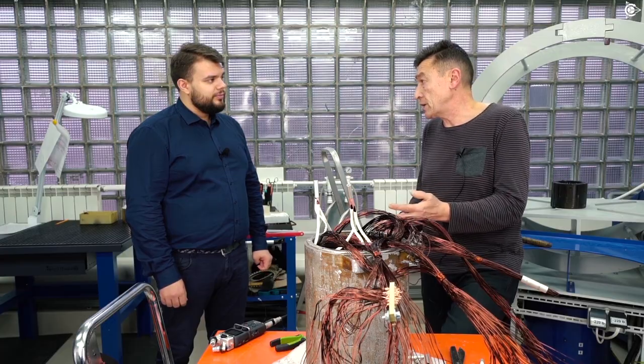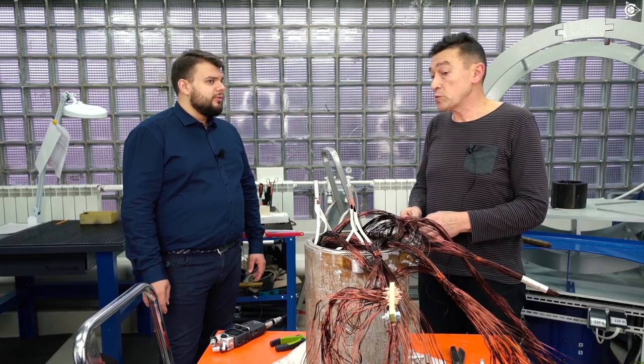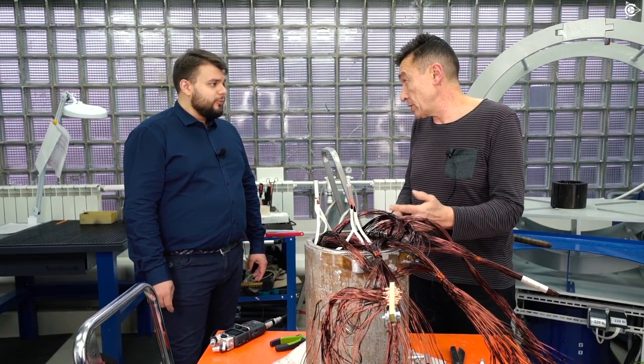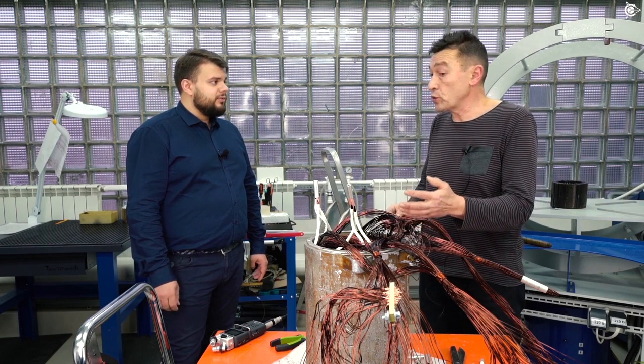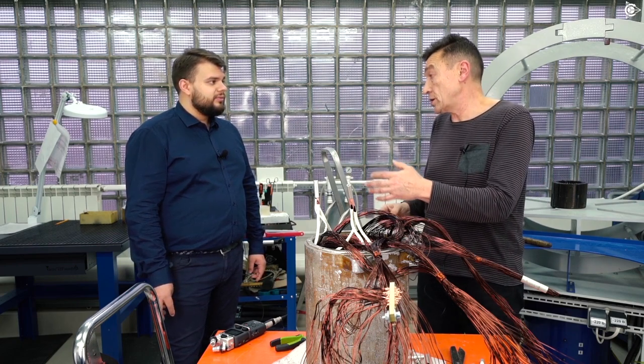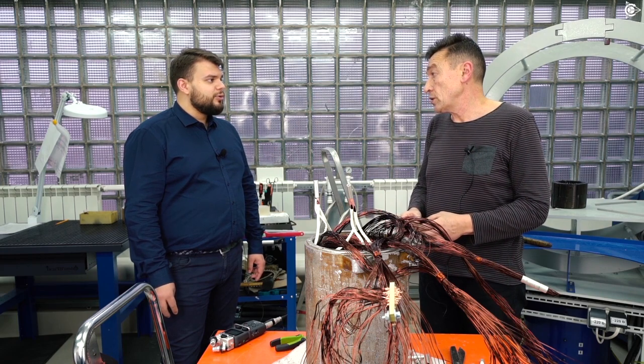Putting it on the compressor is the right approach. A compressor is at least an indicator of reduction on some concrete application. In general, for heavy machinery, this is an indicator that a 7.5 kilowatt motor performs like a 9 or 11 kilowatt one. Well, 11 kilowatt is very hard, but 9 kilowatt for a 7.5 kilowatt hardware will do in terms of current density - it will cope with that 9 kilowatt load.